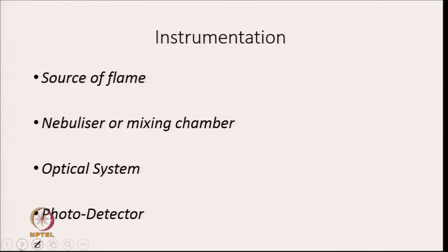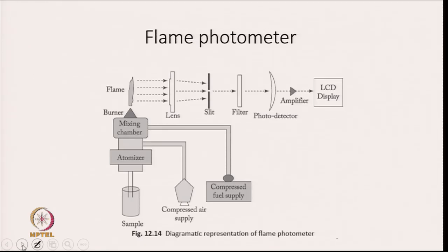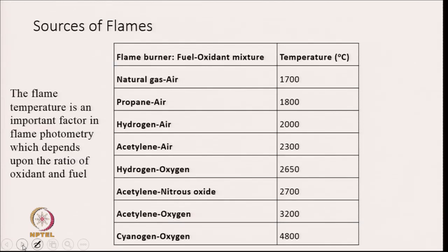The instrumentation of a flame photometer has four important components: a source of flame, a nebulizer or mixing chamber, an optical system, and a photodetector. A typical flame photometer has the sample fed into an atomizer, mixed with fuel in a mixing chamber, burned to produce a flame, then passed through a lens and slit, through a filter, and finally to an amplifier with LCD display.